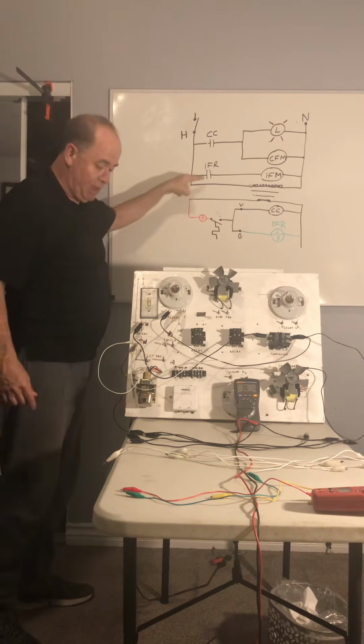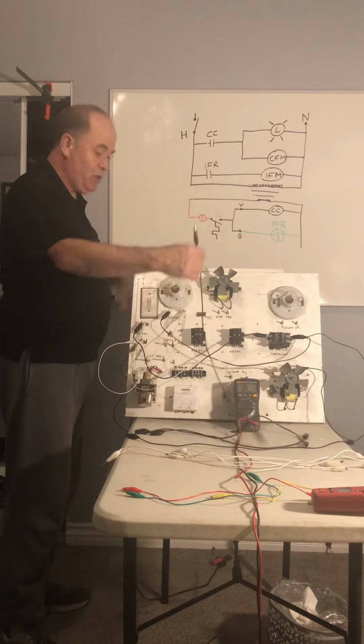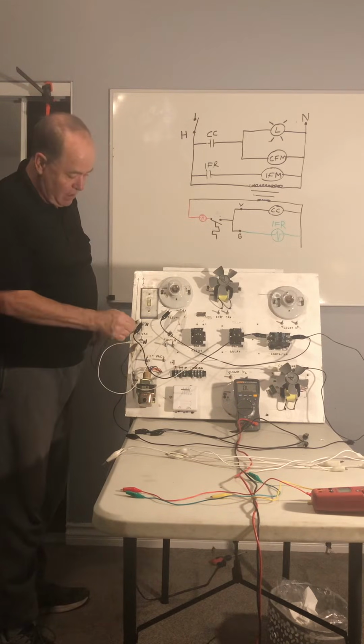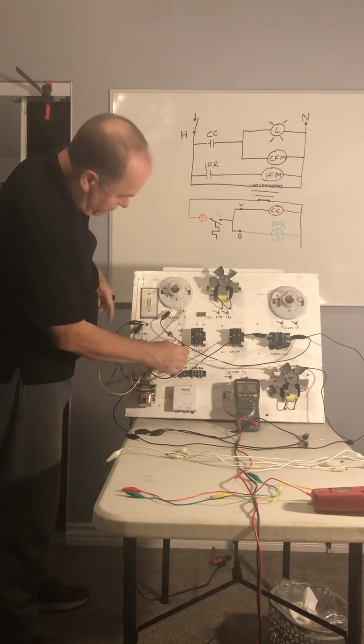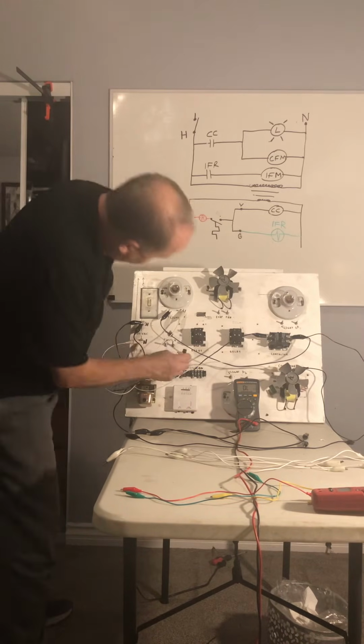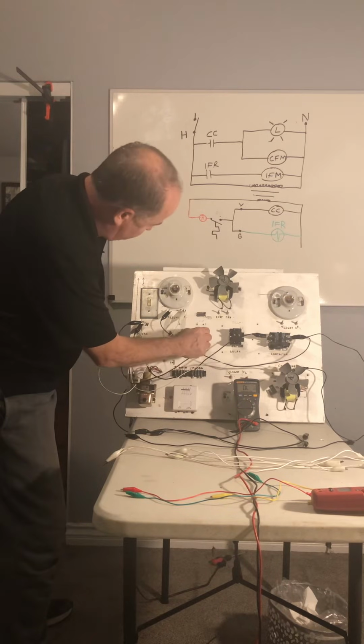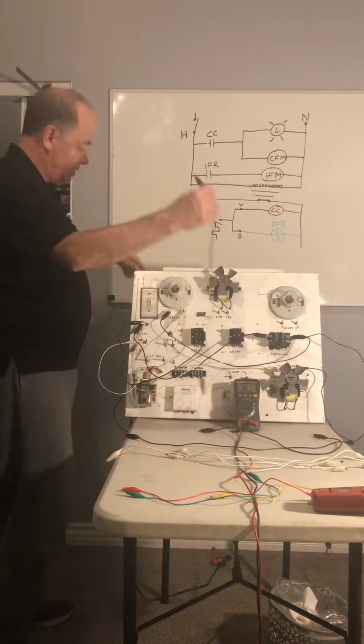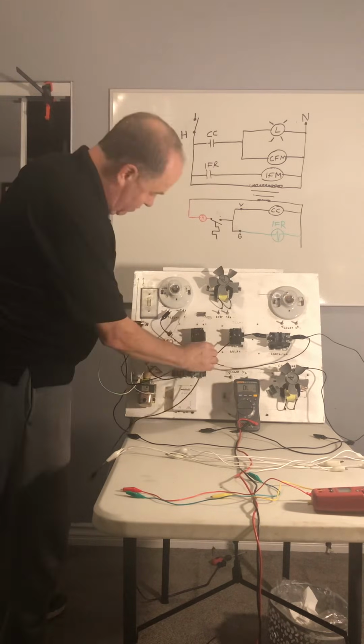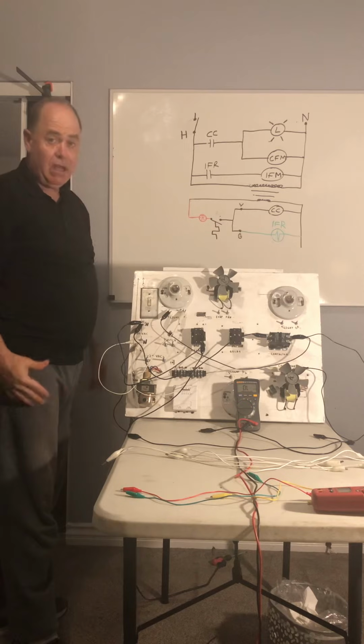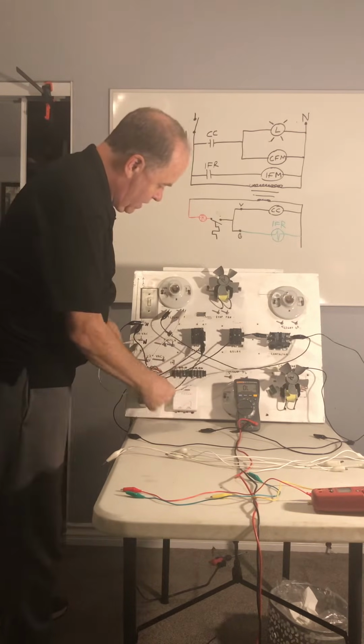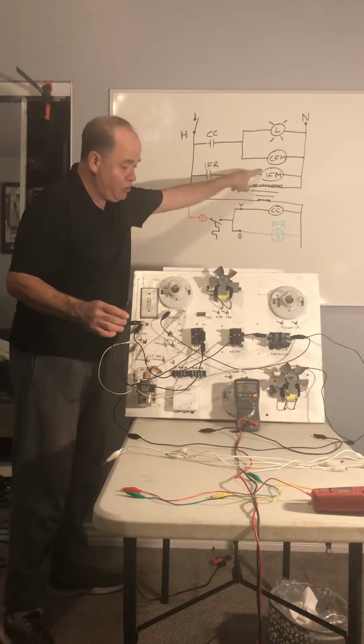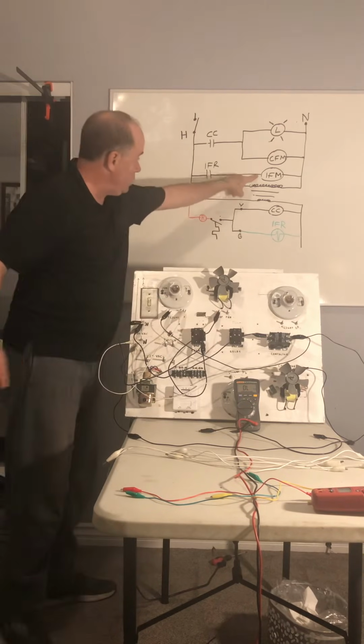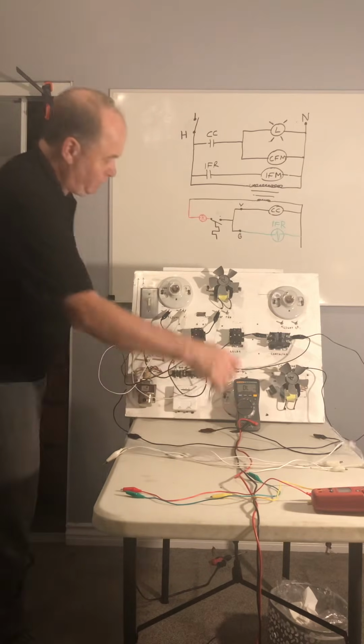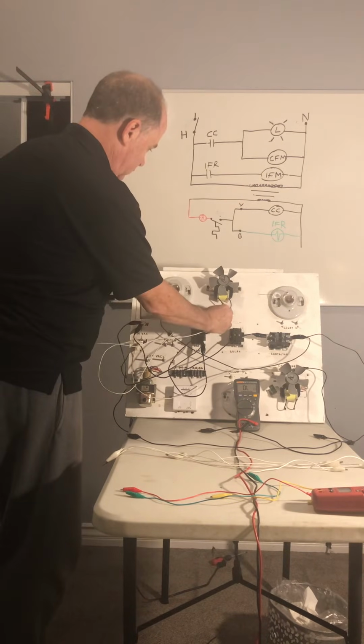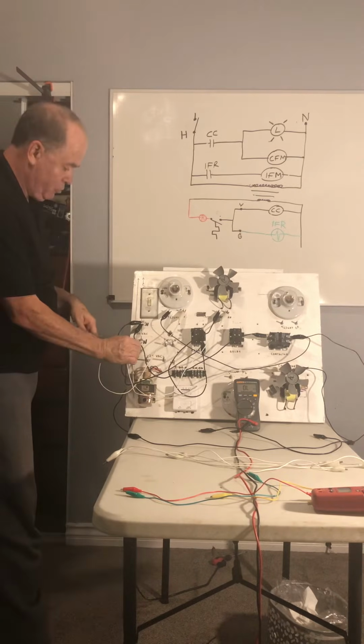Now we also see that we have power coming off of the hot here and going to an indoor fan relay contact. Let's come off the hot and go to our indoor fan relay contact right here, and it's normally open here, and we're coming off it. It wouldn't matter if we went in this way or that way because it is alternating current. And we come off of this, and now we're going to go to the indoor fan motor or evaporator fan motor here. And now we're going to go back to neutral.